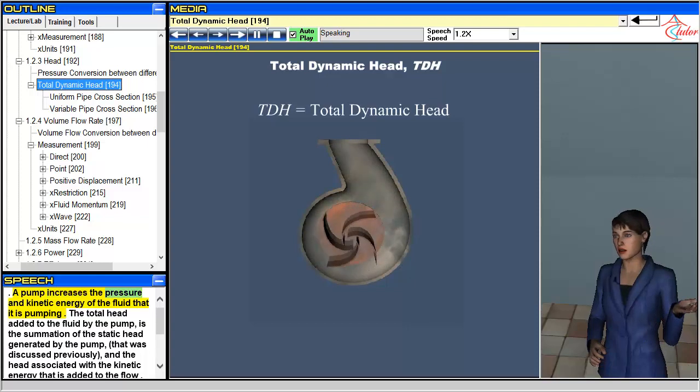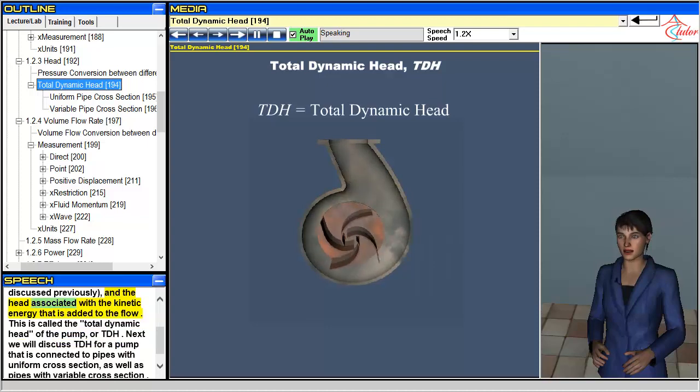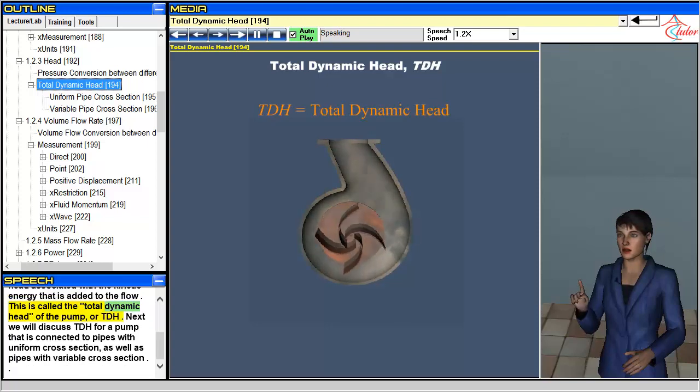A pump increases the pressure and kinetic energy of the fluid that it is pumping. The total head added to the fluid by the pump is the summation of the static head generated by the pump that was discussed previously, and the head associated with the kinetic energy that is added to the flow. This is called the total dynamic head of the pump, or TDH.